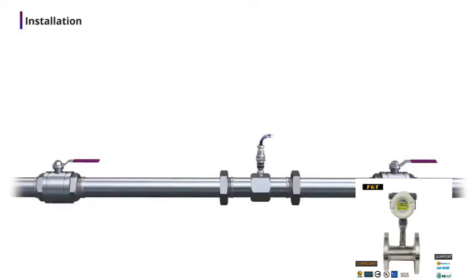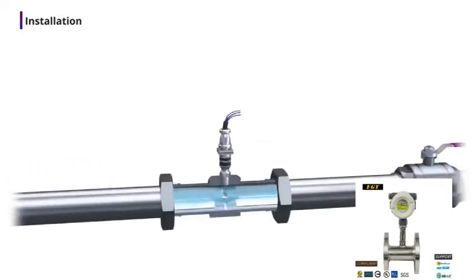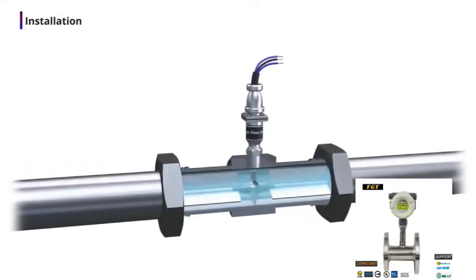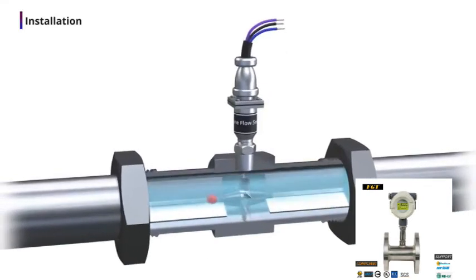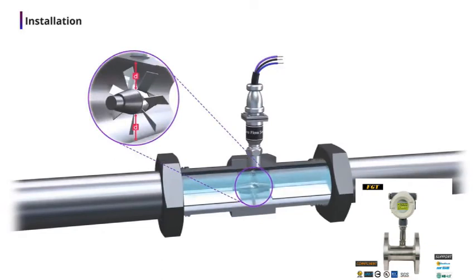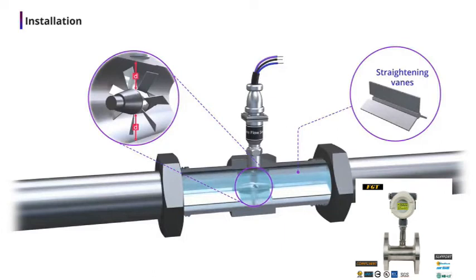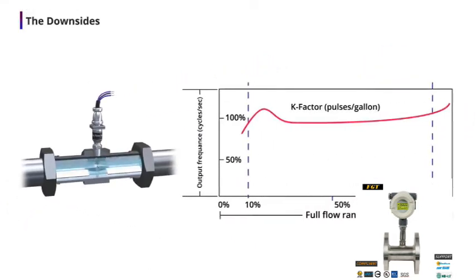Typical installation requires 10 pipe diameters upstream of straight pipe and 5 pipe diameters downstream. The turbine meter can only be used in clean, lubricating fluid, because suspended particles can easily damage the device. The turbine rotor must be positioned in the exact center of the flow, and laminar flow is critical, often requiring straightening vanes. Even though they are one of the most accurate volumetric flow meters in use today, they do have some downsides. The K-factor is not always consistent across the entire flow rate measurement range.